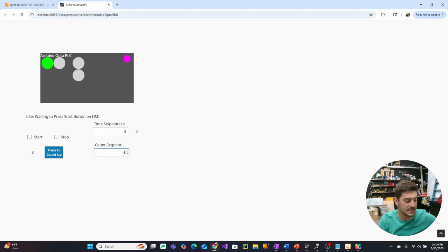Okay, we can pretty easily say, let's make the count set point 11. Let's make this time set point 7. And let's do it again. Let's press start here. Let's flip the hand switch. We're going to get to 7 seconds. We're going to count up to 11 clicks. And now we've finished the sequence. We can hit stop. And we're back to idle.